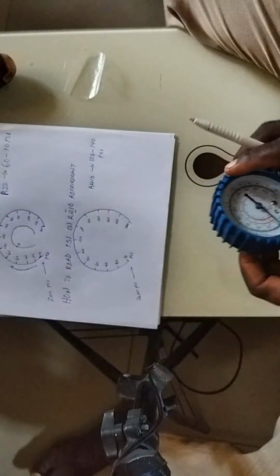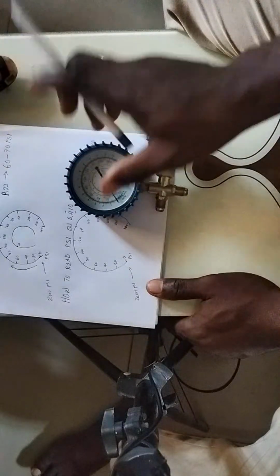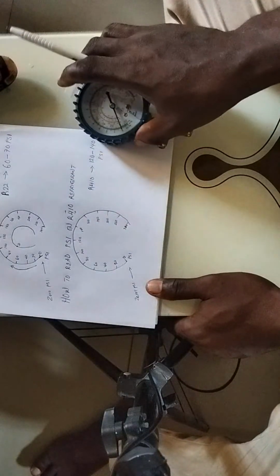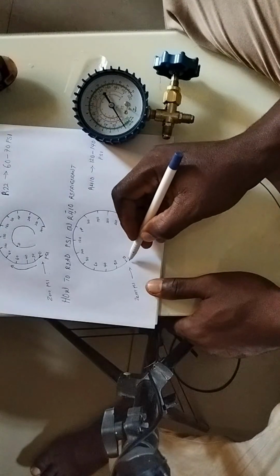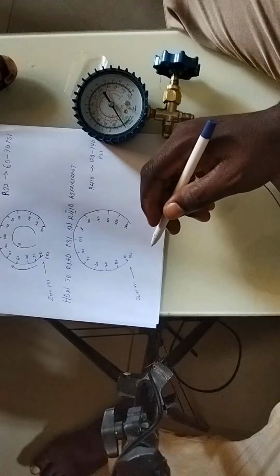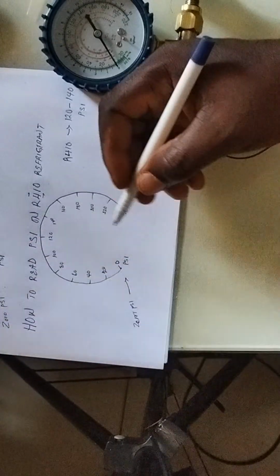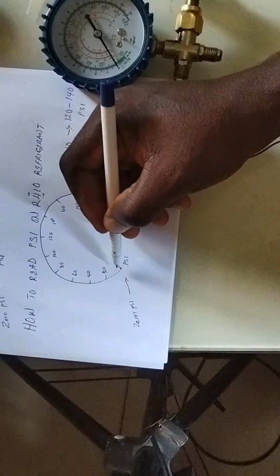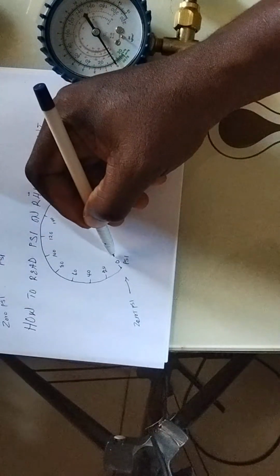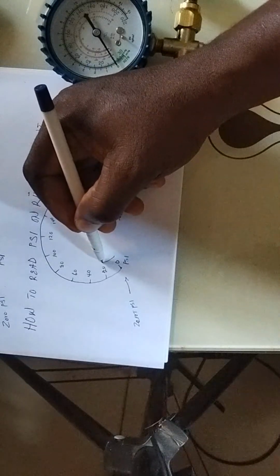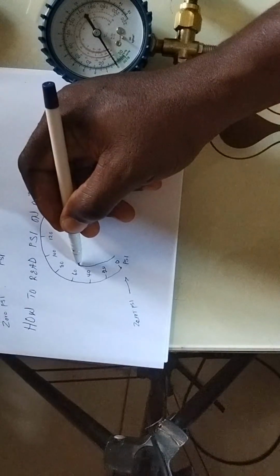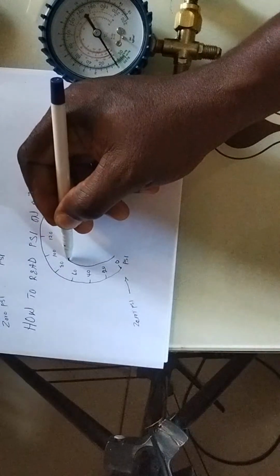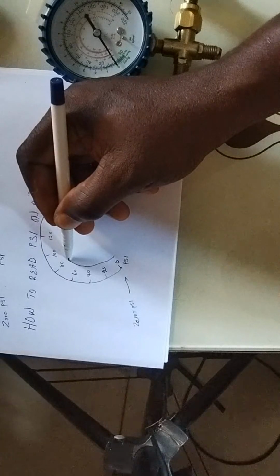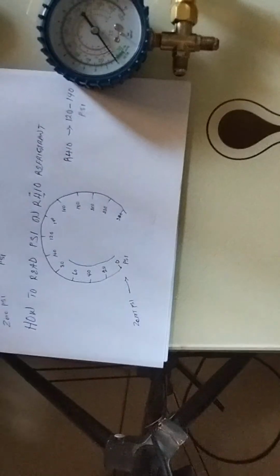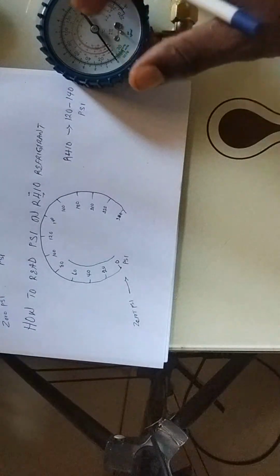So let's continue with what we were saying about R410 refrigerant. If you are charging R410 refrigerant from point 0, this is from point 0 at 0 psi, you have this, understand? When you keep charging R410 refrigerant from point 0, you increase it to 20, you increase it to 40, you increase it to 60, you increase it to 80. At this 80, that is where you start observing expansion. When I mean expansion, you notice that the discharge line on the air condition will start freezing.